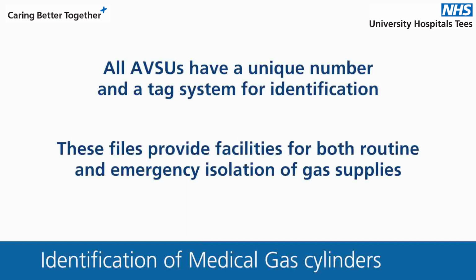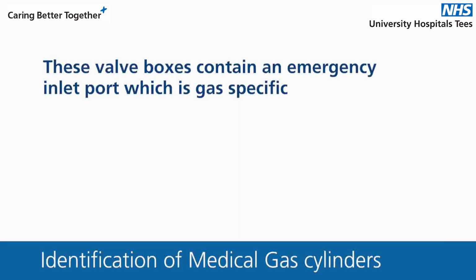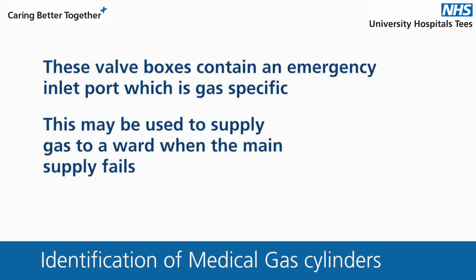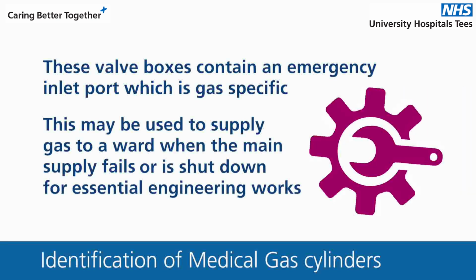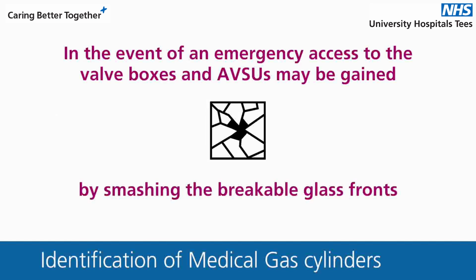These valves provide facilities for both routine and emergency isolation of gas supplies. These valve boxes contain an emergency inlet port, which is gas-specific. This may be used to supply gas to a ward when the main supply fails or is shut down for essential engineering work. In the event of an emergency, access to the valve boxes and AVSUs may be gained by smashing the breakable glass fronts.